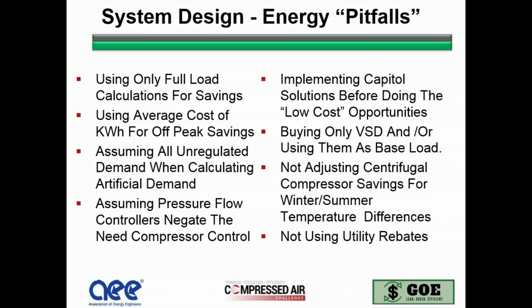Implementing capital solutions before you do the low-cost opportunities. Again, you want to take care of those low costs before you spend a lot of money. Buying only VSDs and or using them as a base load. They are not designed for base load machines, and they are inefficient as a base load machine. So they're very efficient at partial loads. You need to have base load units in your system as well.